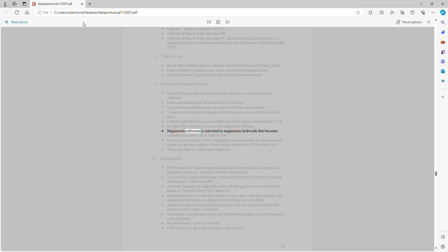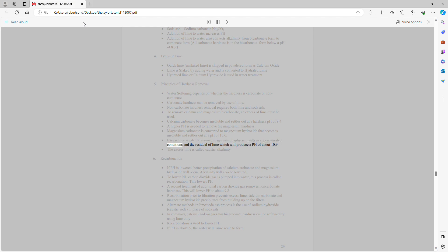Magnesium carbonate is converted to magnesium hydroxide, which becomes insoluble and settles out at a pH of 10.6. Excess lime needed to remove magnesium hardness results in supersaturated conditions and a residual of lime which will produce a pH of about 10.9. The excess lime is called caustic alkalinity.